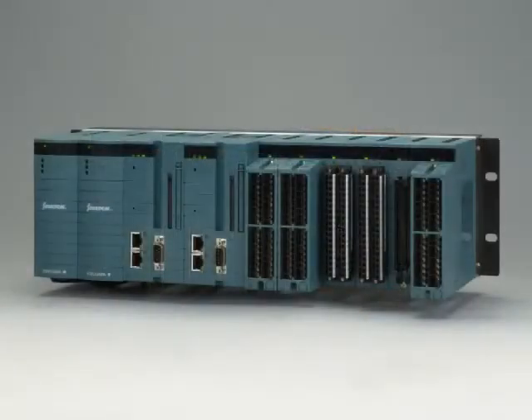Second is FCN. It is a 19-inch rack-mountable controller and can be expanded up to three nodes. It can have redundant power supplies, CPUs, buses, and some IO cards such as Foundation Fieldbus cards. Each CPU has two built-in Ethernet ports, which give the controller great flexibility for network connection. Expandable IO cards and hot-swappable components make FCN a highly reliable, flexible, and powerful process controller.